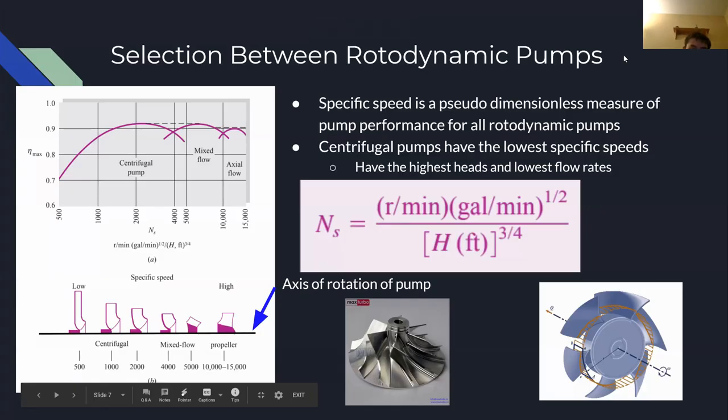Centrifugal pumps are just one of many different types of rotodynamic pumps, and these pumps are differentiated by the specific speeds at which they most effectively operate. Centrifugal pumps have the lowest specific speeds, which means they operate best at high output heads and low output flow rates.